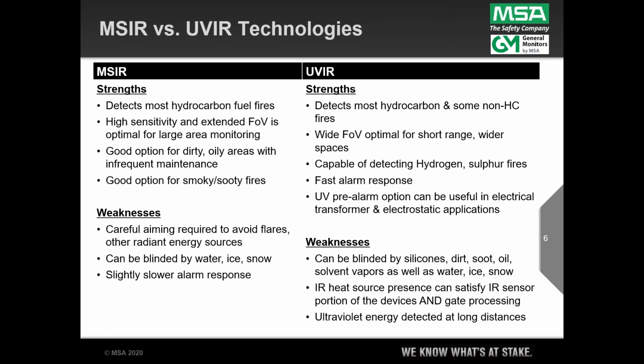So I wanted to first, though, just do a quick comparison head-to-head, strengths and limitations of MSIR on the left, strengths and limitations of UVIR on the right. And so I'll just start with MSIR strengths. This is a hydrocarbon-only fire detector. I talked about that. Talked about the higher sensitivity, the extended field of view. It's optimal for large area monitoring. And where do we see these? We see these in aircraft hangars and in large warehouses and places where that field of view is a benefit. And maybe it can, with that extra range, again cover the area with fewer devices in some cases.